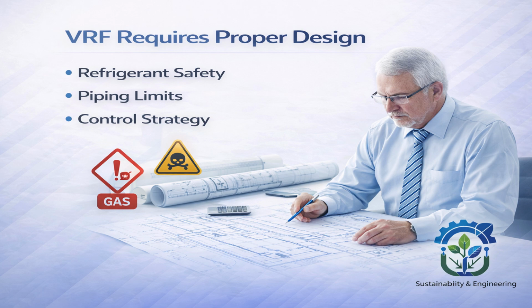VRF is a powerful system, but only when it is designed properly. Many VRF failures are not equipment failures, they are design failures. Let's go through the three most critical design considerations. First, refrigerant safety. VRF systems use large quantities of refrigerant. Unlike chilled water systems, this refrigerant passes through occupied spaces. So as engineers, we must always ask, what happens if there is a refrigerant leak? Standards like ASHRAE 15 and ASHRAE 34 define maximum allowable refrigerant concentration and safety limits for occupied spaces.